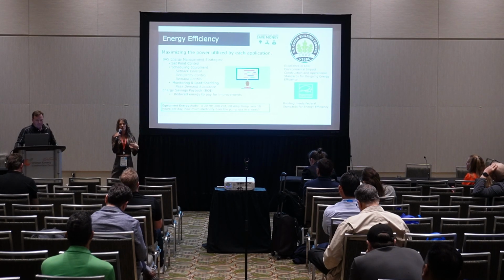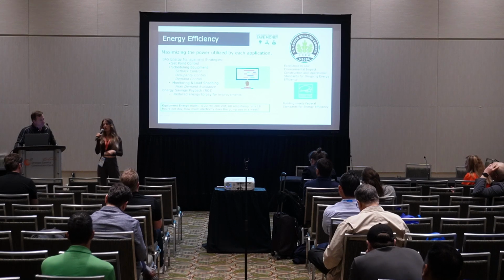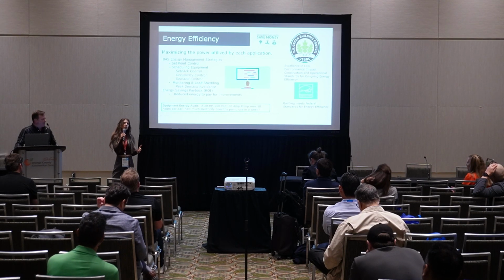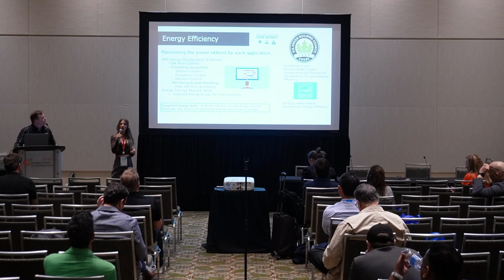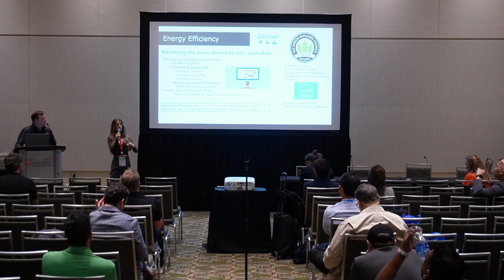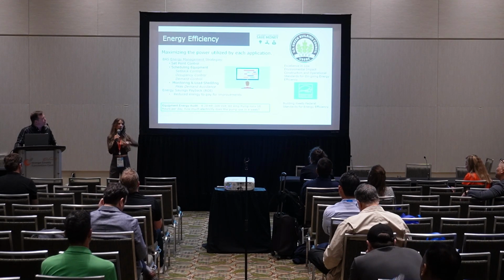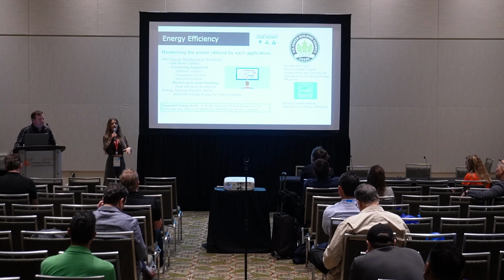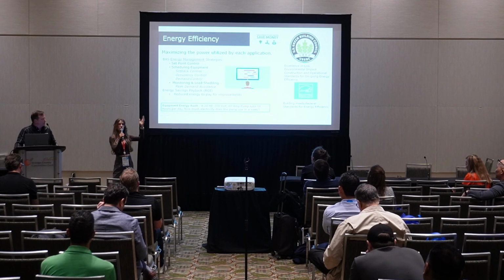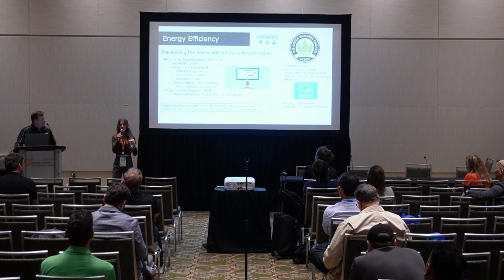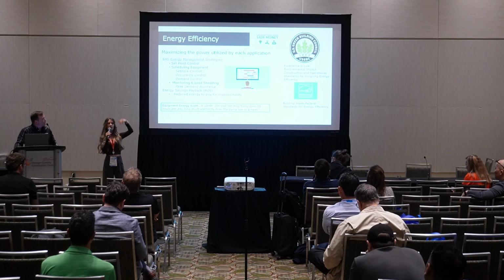I didn't put any pictures in here, but for example, I've done about five of these now: water source heat pump loops. It's a hydronic loop with water source heat pumps in the spaces, heated by a gas boiler and cooled by a cooling tower. That's not an uncommon system, and I have never gone into one of those and had it be working properly. It's always cycling, overshooting and then cooling, overshooting and then cooling.